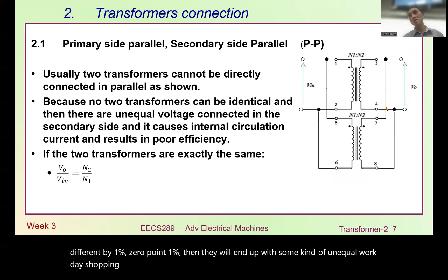But of course, many people still do that. They assume the two transformers are exactly equal. But the problem is if they are slightly different in conversion ratio, maybe by 1% or 0.1%, they will end up with some kind of unequal voltage shorting together, which causes additional losses.